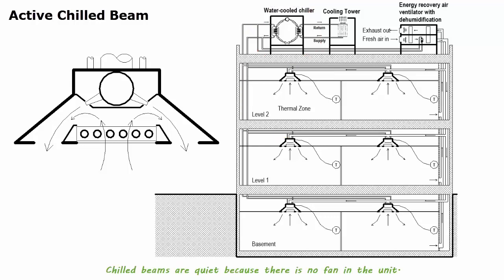Chilled beams are quiet because there is no fan in the unit. Air duct size is much smaller than the conventional all-air systems because it only needs to move the amount of air required for maintaining indoor air quality. The smaller duct can reduce the interstitial space height to save cost and/or increase ceiling height. As cooling is primarily delivered by water piping throughout the building, it reduces the fan power to move air and the energy loss through ductworks. Disadvantages are high initial costs and a high level of humidity control of the incoming air.